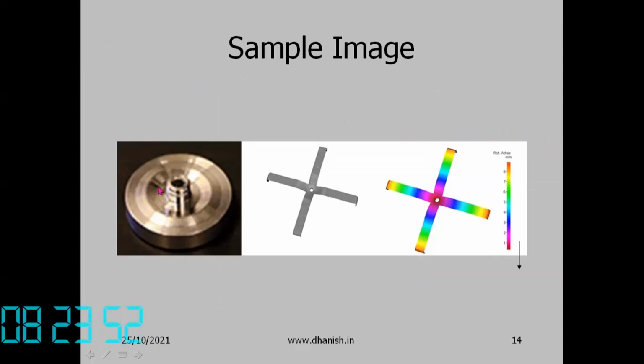So the sample image from this instrument is shown here. The range of the instrument is much better. We can measure even small objects like this, the height of the object. In order to save time, we are not measuring the entire area. We skip some of the area and we get these various heights of the surface. If you want, we can capture the entire area. Of course, we can capture small portions and stitch them together. All that is possible in software.